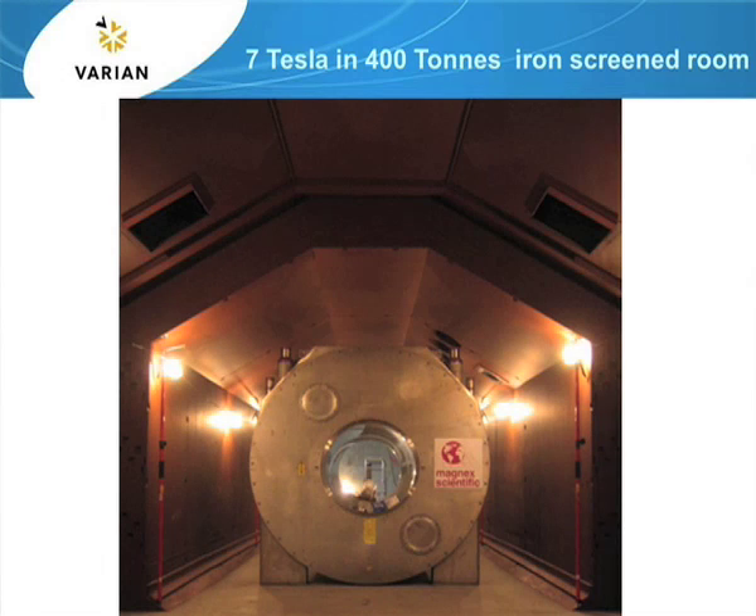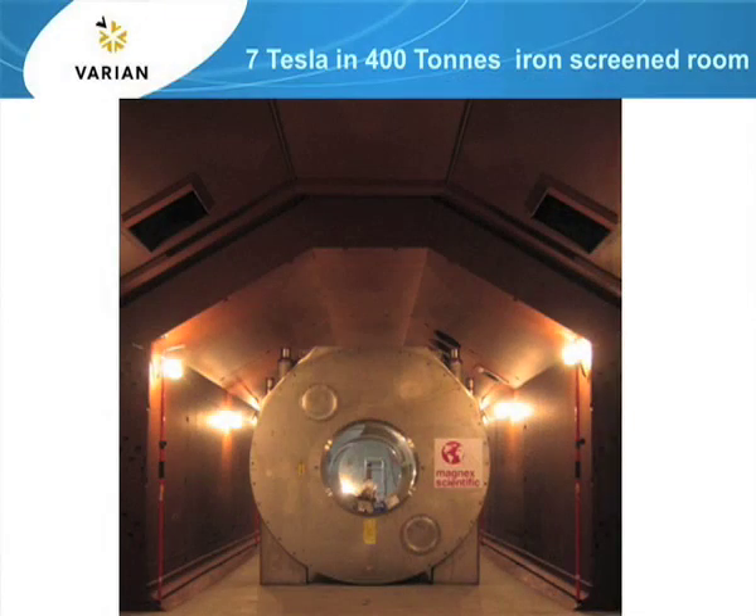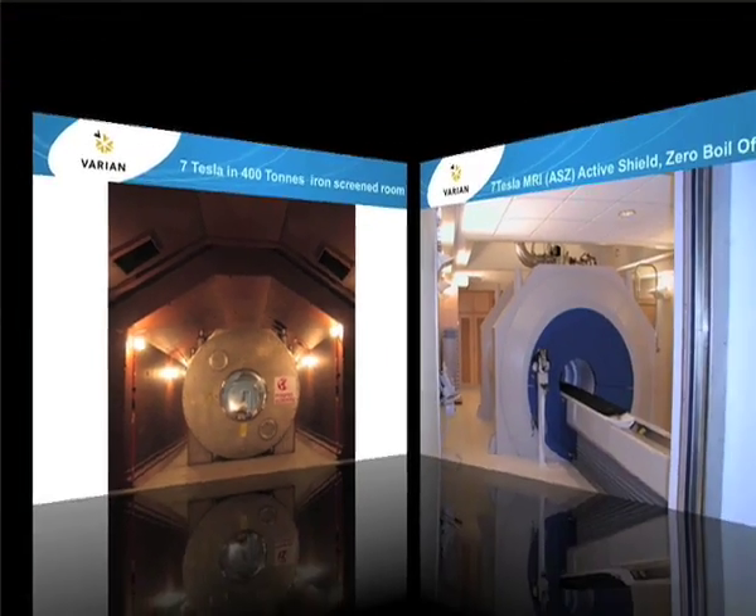That shows a picture of a 7 Tesla whole-body magnet. The magnet itself is not actively screened, so without some additional shielding the stray field goes out about 40 feet, and the five-gauss line is about 40 feet away from the magnet. This picture shows the magnet in an early part of installation, sitting inside a 400-tonne iron screen room. The purpose of the room is purely to contain the stray field.